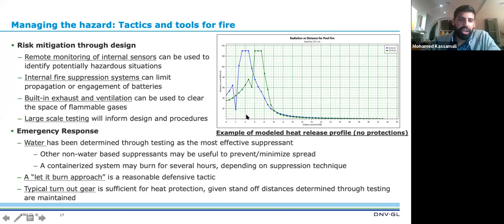There's also built-in exhaust and ventilation systems which, prior to a fire happening and upon detection of a gaseous volume, whether it be hydrogen or carbon monoxide, some systems are capable of triggering the HVAC system or other exhaust ventilation to move those flammable clouds out of the container and only introduce fresh air to the system, to avoid an environment conducive to a fire or explosion.